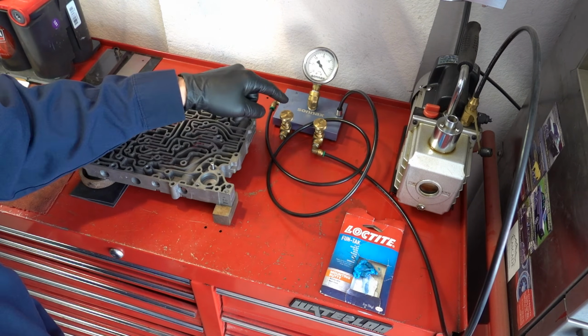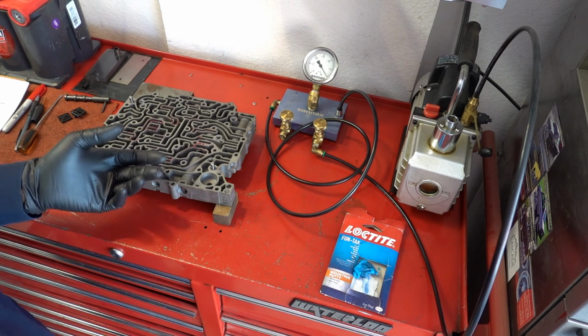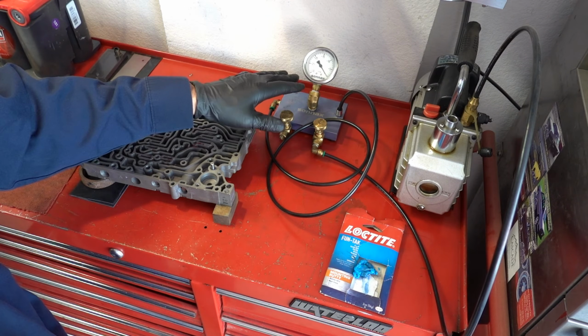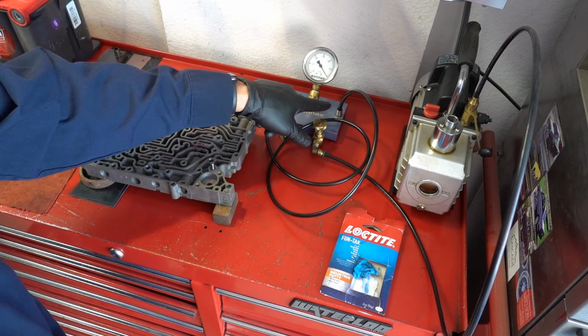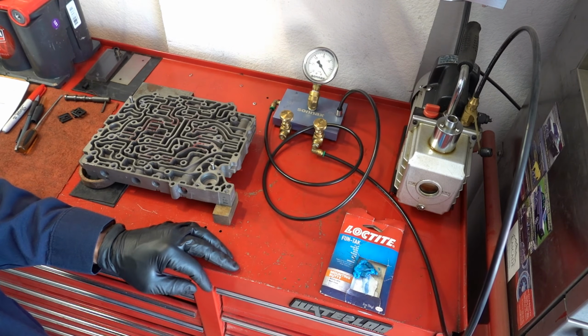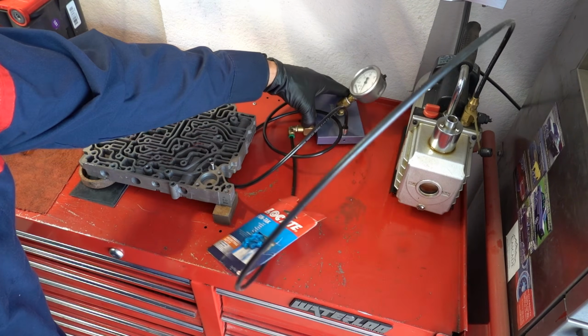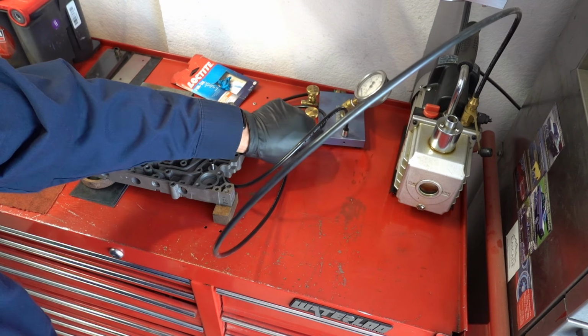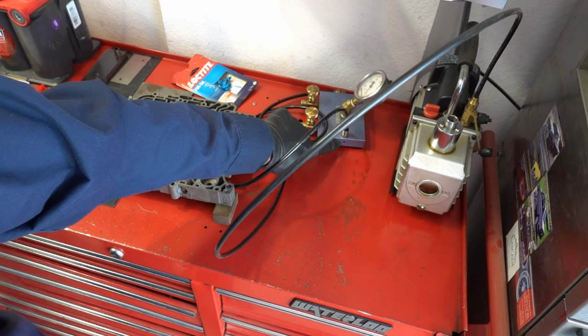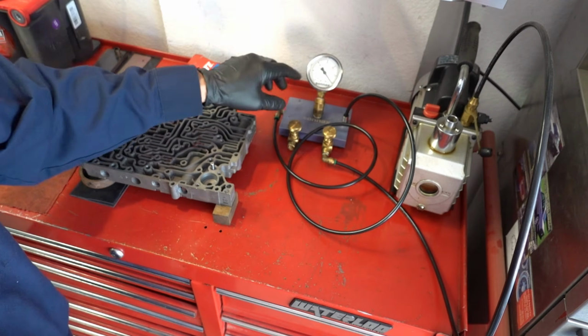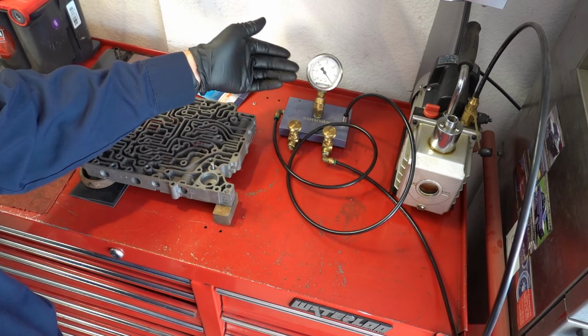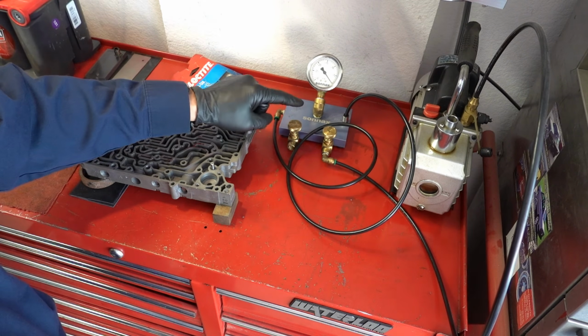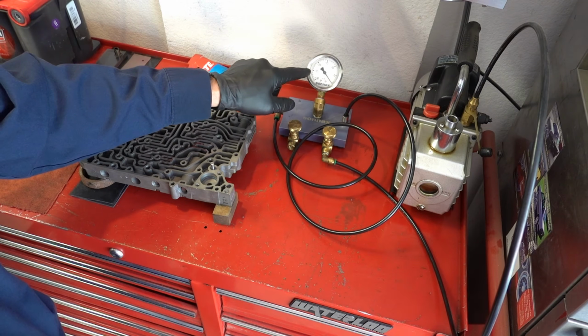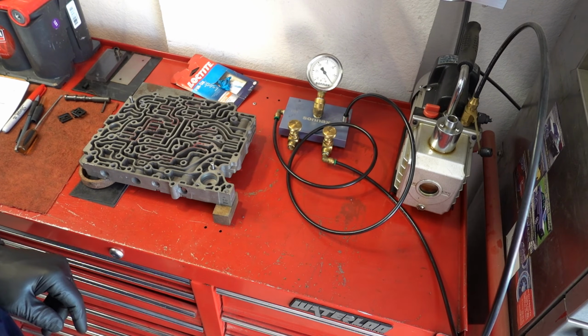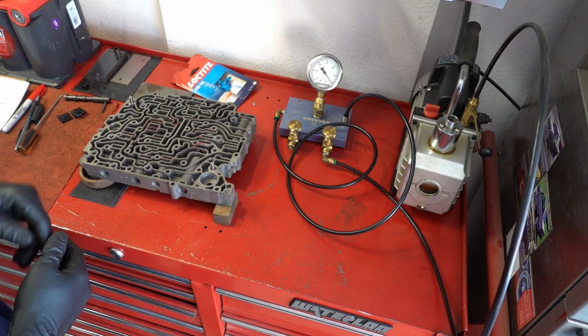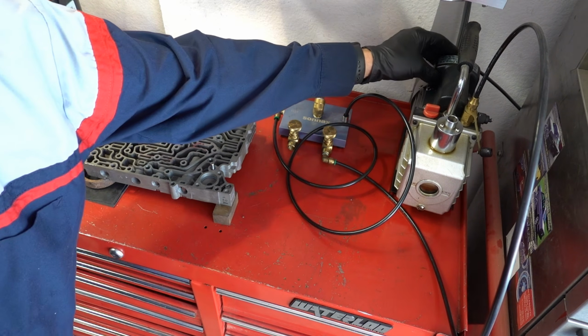So you're going to use your pump valve and your bleeder valve to dial in your calibration. You want a base of 5 inches of calibrated vacuum when you turn this machine on with this test lead plugged into the calibration receptacle. Then when you turn the machine sideways, you'll notice a calibration port right here. You plug that port with a finger, and you watch the needle jump up from 5 inches to somewhere between 20 and 30 inches. You want to dial this bleeder valve, adjusting it until you get a steady 25 inches of vacuum when your finger is on the calibration receptacle. So we'll go ahead and calibrate it now.